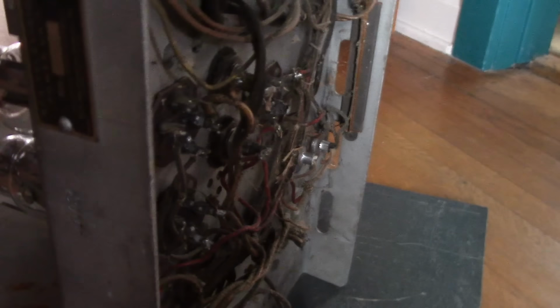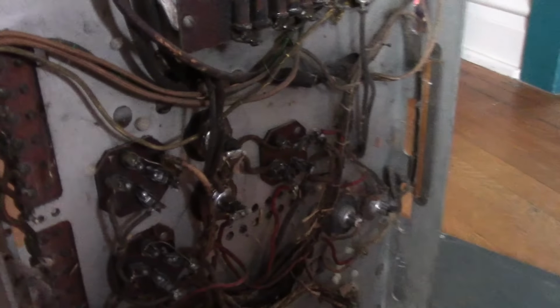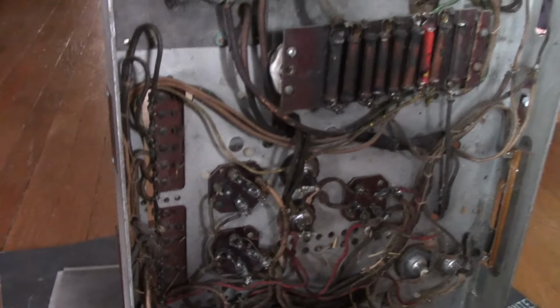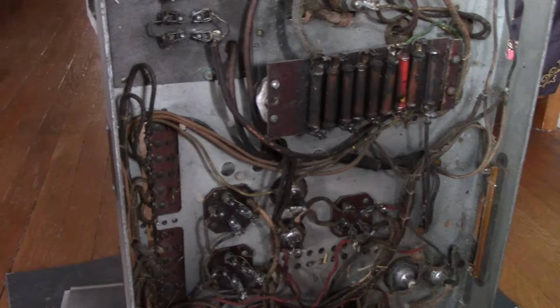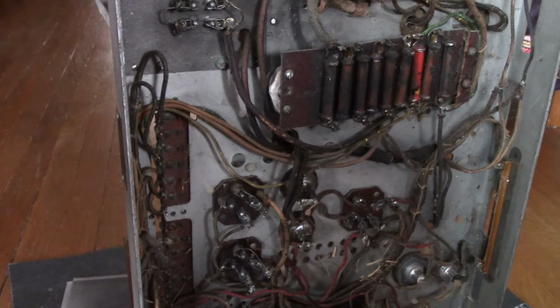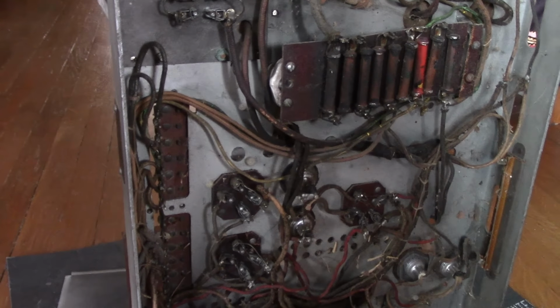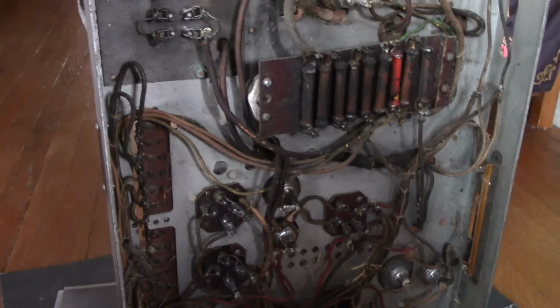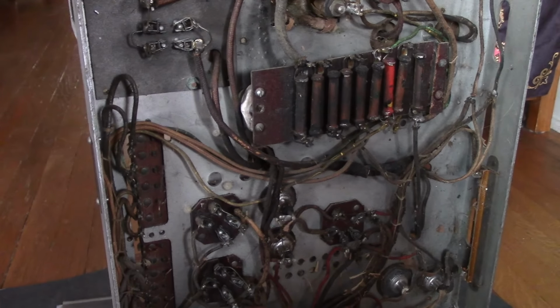So that rheostat, I believe, is in series with the primary on that high voltage transformer. As you vary that control, it alters the primary, like a variac, and it's going to vary the high voltage output. However, you also need a filament supply for the high voltage rectifier tube.